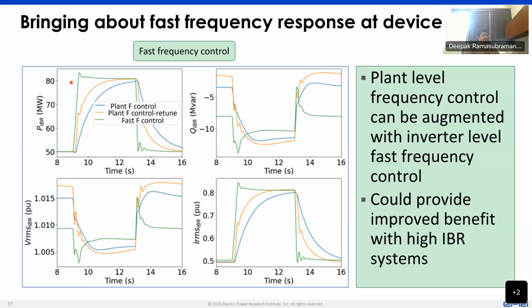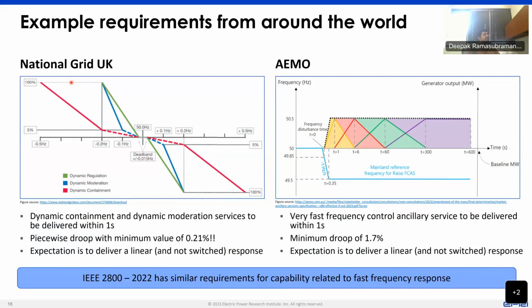Now, with respect to inverter level frequency control, there have been instances around the world wherein this kind of capability has been required for a few years. One example is from National Grid UK, where they have a market-based requirement where an inverter manufacturer could choose to provide services such as dynamic containment and dynamic moderation, where the full response is expected to be delivered within 1 second. And there is a piecewise droop characteristic, which can have a minimum value of as low as 0.2%. So 0.2% of droop response delivered within 1 second. And the expectation is to deliver it in a linear manner and not in a switched manner.